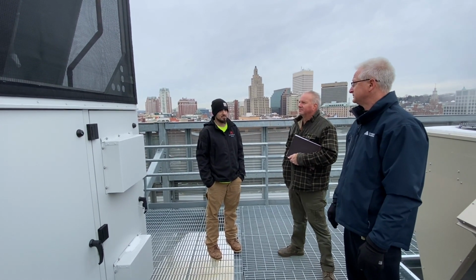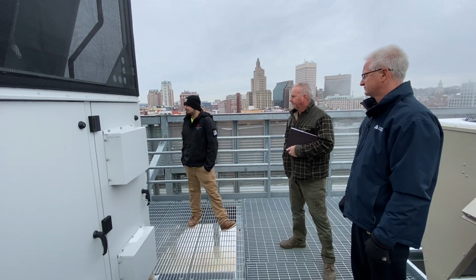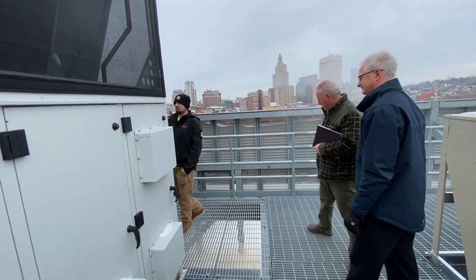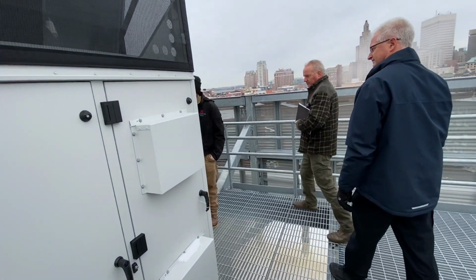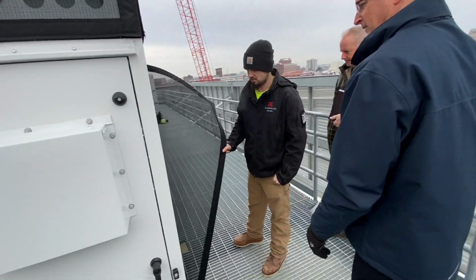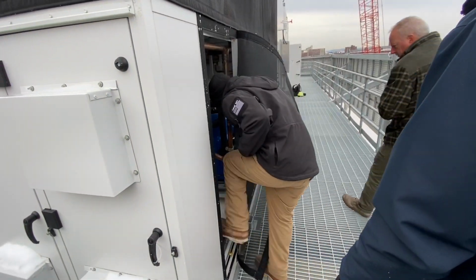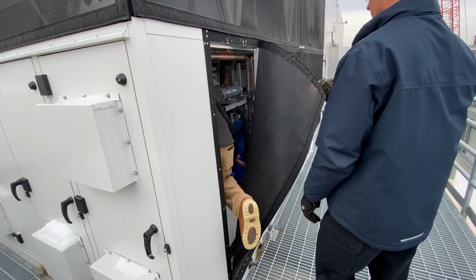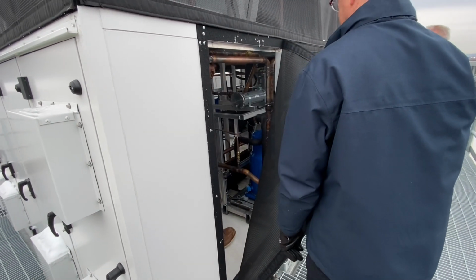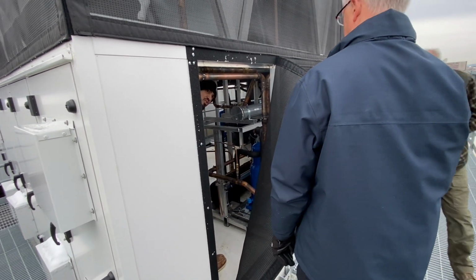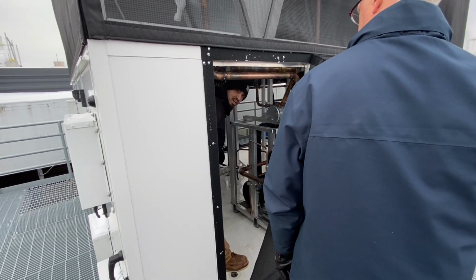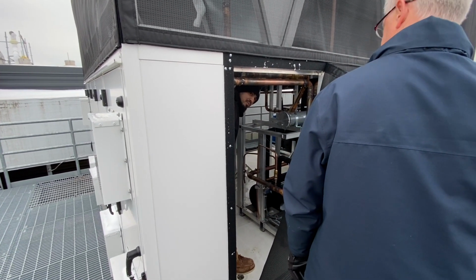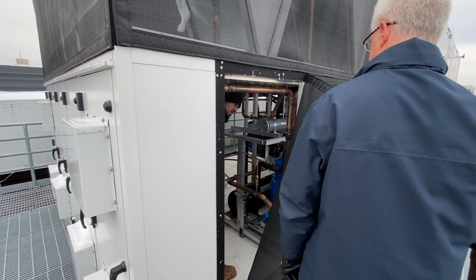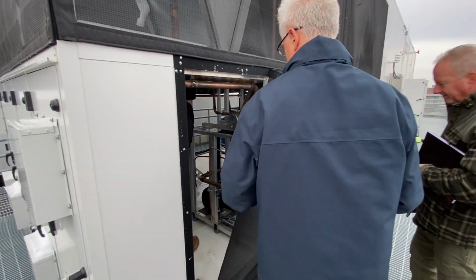They should have manual reset low pressures and high pressures, I believe. What about freeze stats? Any freeze stats on this unit? There's no chilled water, it's all DX cooling, so we shouldn't have any coils to protect from freezing. That'll be the manual reset he's talking about, low suction, just on the compressor side.